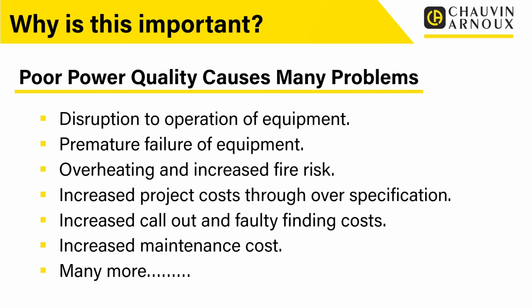Increased call outs and fault finding costs. A lot of times, all this nuisance tripping of items or things just resetting for no reason, a lot of that can be down to power quality, and we can use the power quality techniques to actually improve the way we do that and minimize the downtime. Obviously, increased maintenance costs. Again, if we're getting things overheating, we're getting things wearing out quicker, the maintenance costs go up. And as I've put on there, many more.